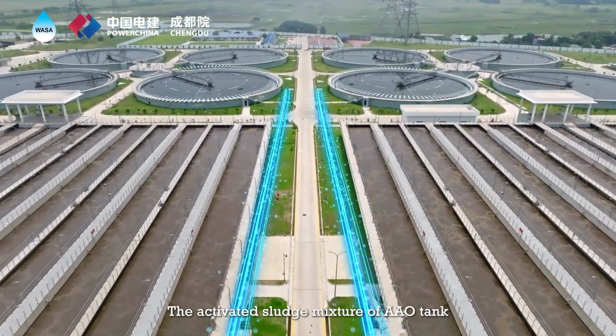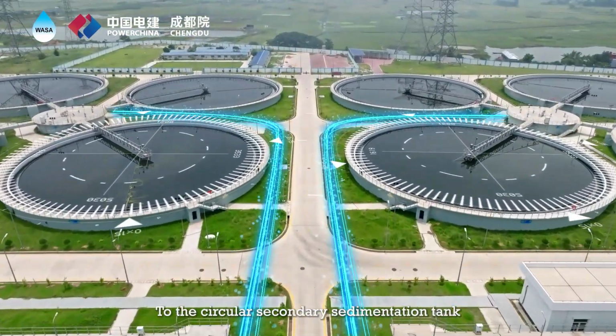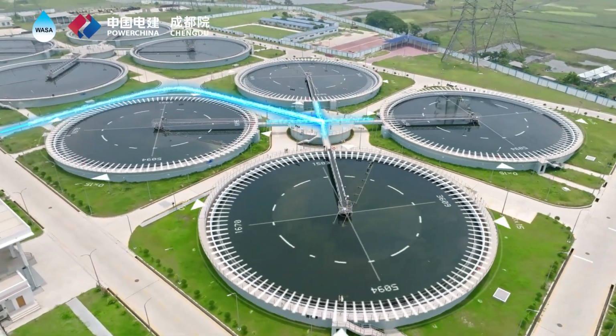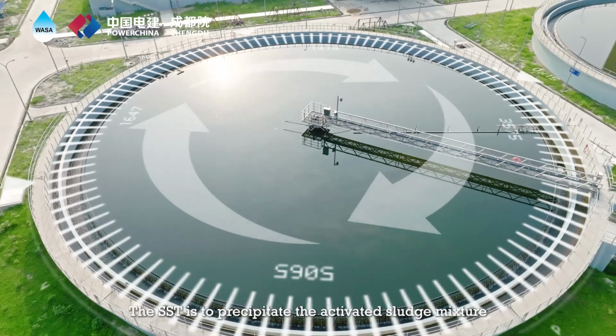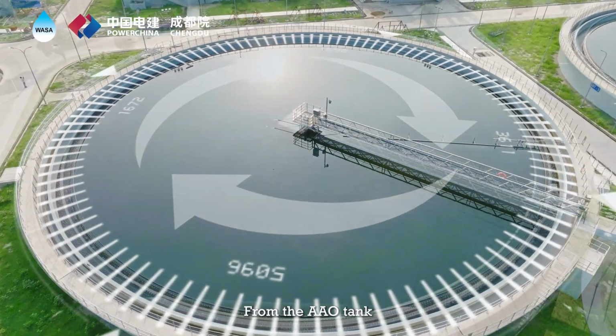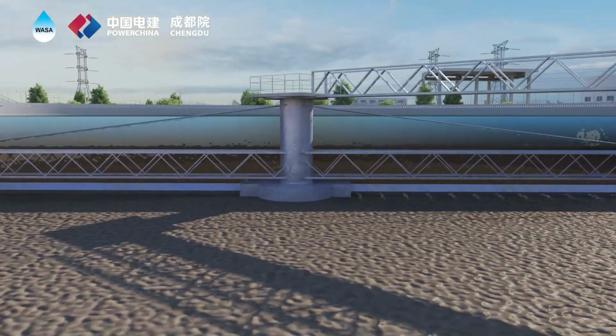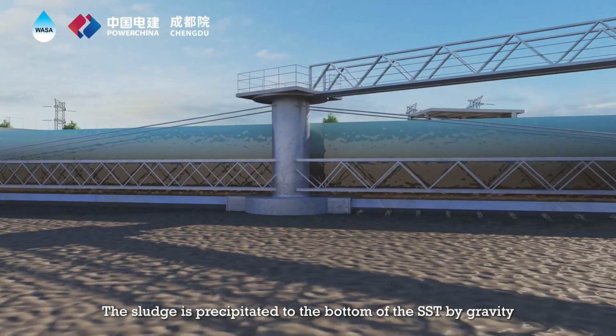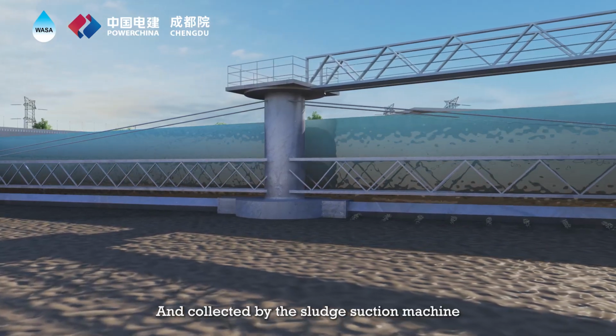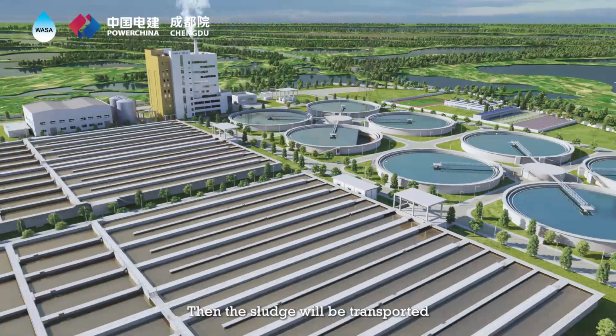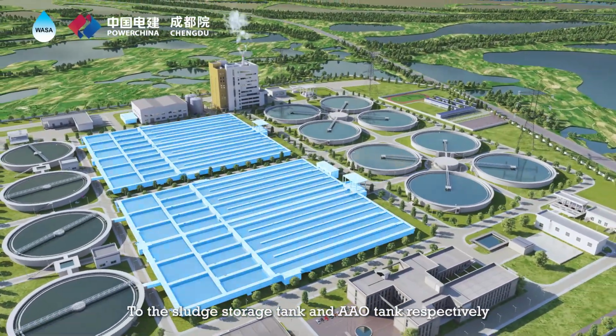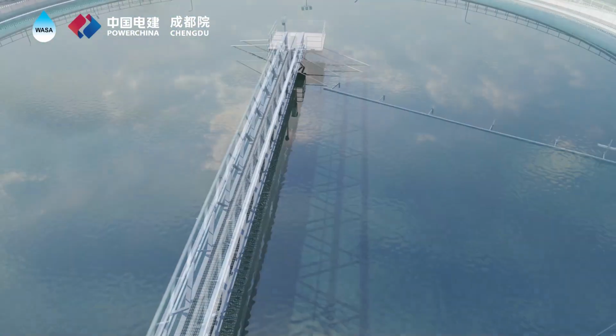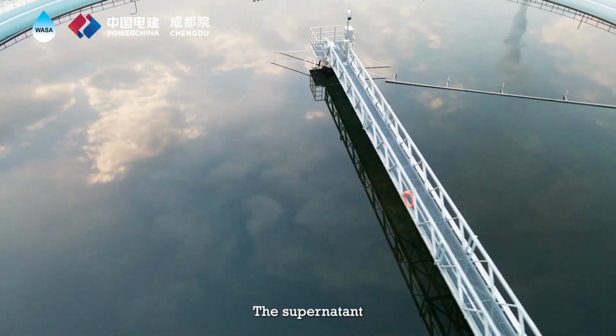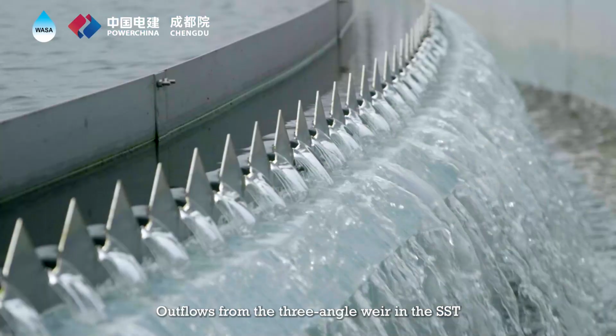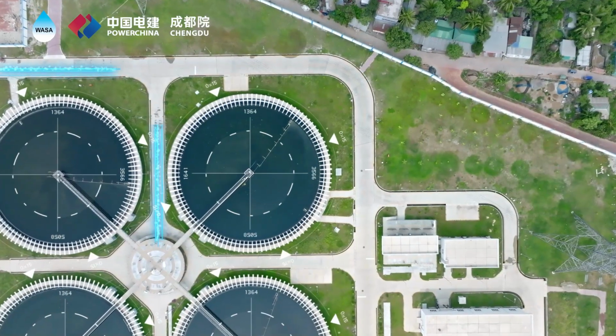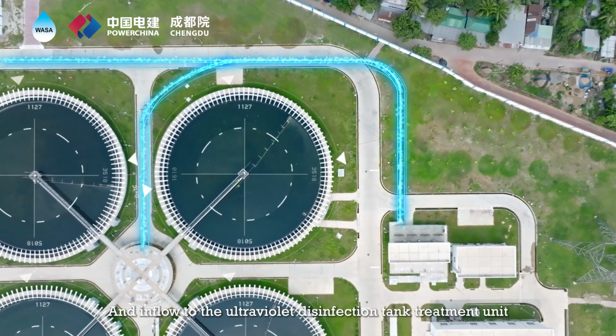The activated sludge mixture of AAO tank is evenly distributed to the circular secondary sedimentation tank by equalization tank. The SST is to precipitate the activated sludge mixture from the AAO tank and finally achieve solid-liquid separation. The sludge is precipitated to the bottom of the SST by gravity and collected by the sludge suction machine. Then the sludge will be transported to the sludge storage tank and the AAO tank respectively. The supernatant, as treated clean water, outflows from the 3-angle weir in the SST and inflows to the ultraviolet disinfection tank treatment unit.